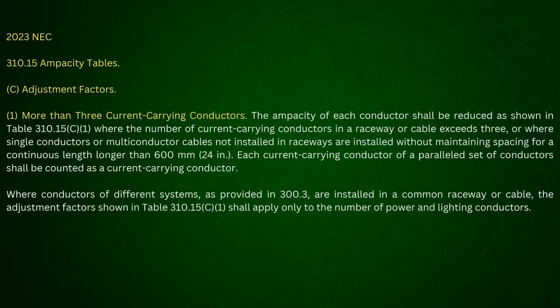Yeah. Oh, okay. So this is another area where I'm using nonmetallic sheathed cable and it's not installed in a raceway. It says, are installed without maintaining spacing for a continuous length longer than 24 inches. Well, hey, wait a minute. That 24 inches is not in a raceway. So how the hell are you going to tell me I don't maintain 24 inches? Because right here, it's telling me where it's not installed in a raceway.